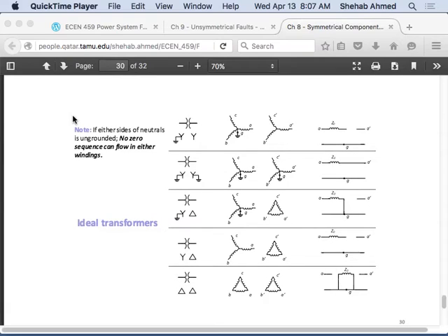We stopped here. I think we went through it now, and this is very important. This slide is very important, except that of course it's missing something: they have the neutrals connected, but they don't have impedances between the neutral and ground.